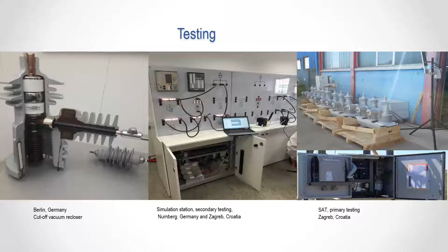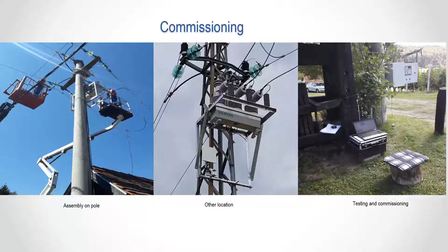So here is the concept of the decentralized solution. When the fault occurs, isolation is below 200 milliseconds, and reconfiguration is below 300 milliseconds. That's the concept, and here are some pictures of vacuum reclosers, testing in Nuremberg and testing in Zagreb. Here are some commissioning pictures, assembling on a concrete pole and on a solid steel pole, and testing and commissioning. And here is one video. In all of the sections we made 2 pole short circuits and 1 pole short circuit. And in each section we put power quality devices to measure the time of interruption.